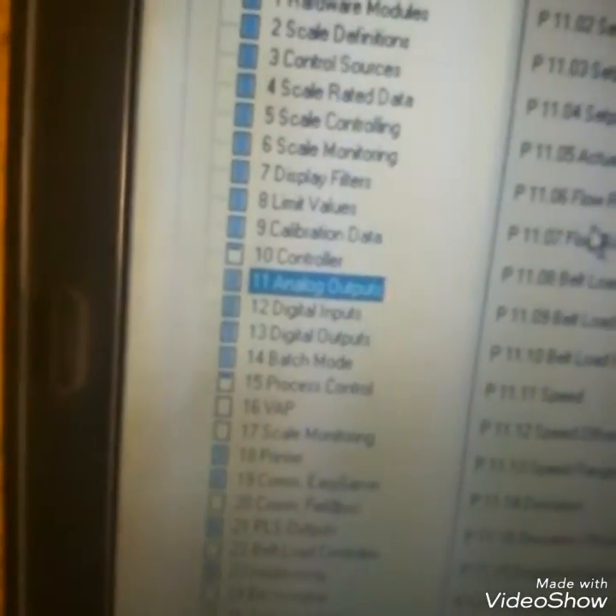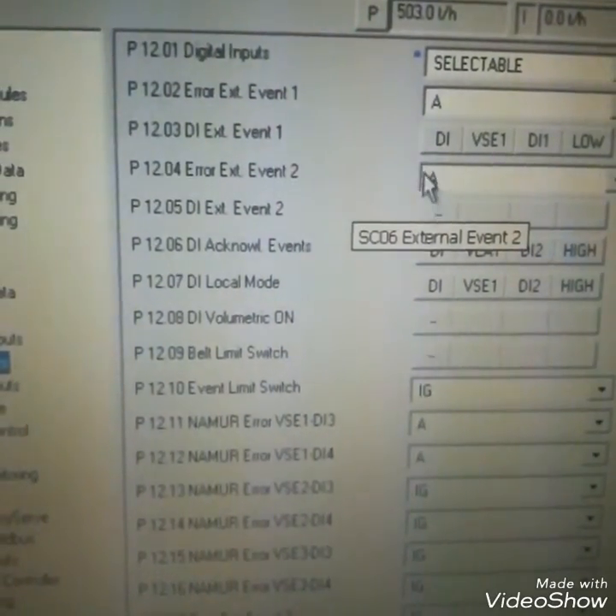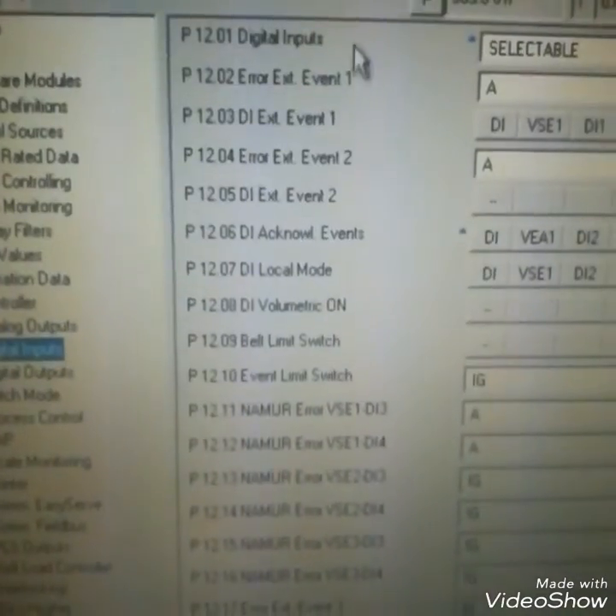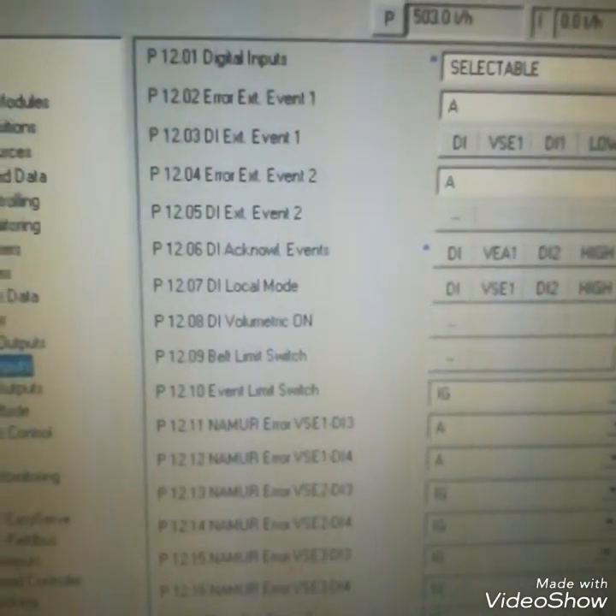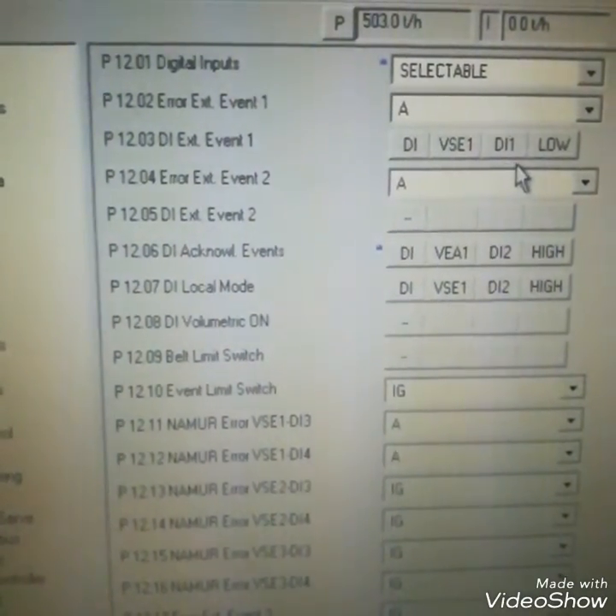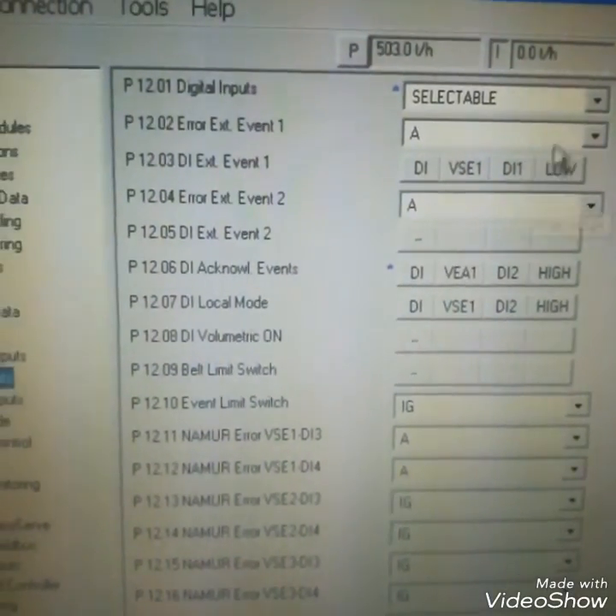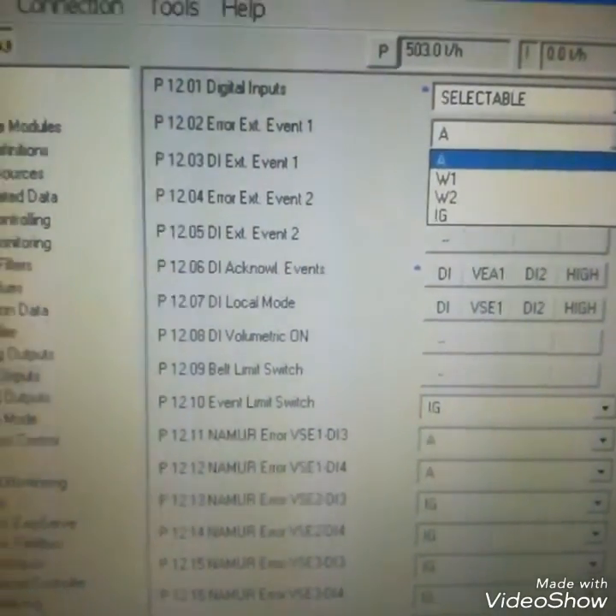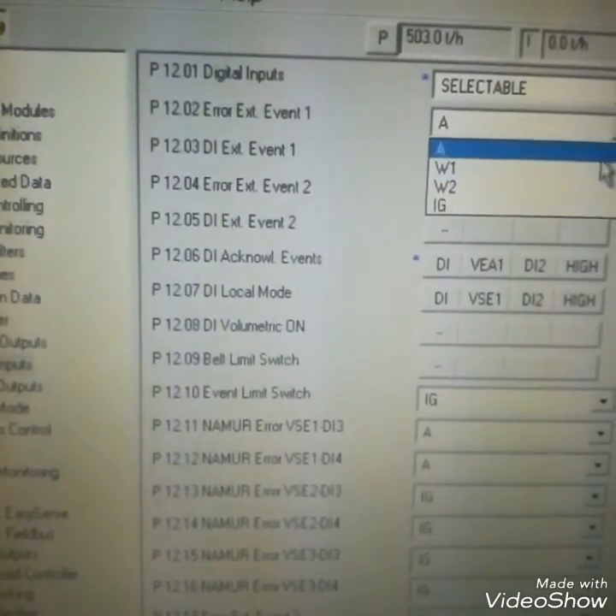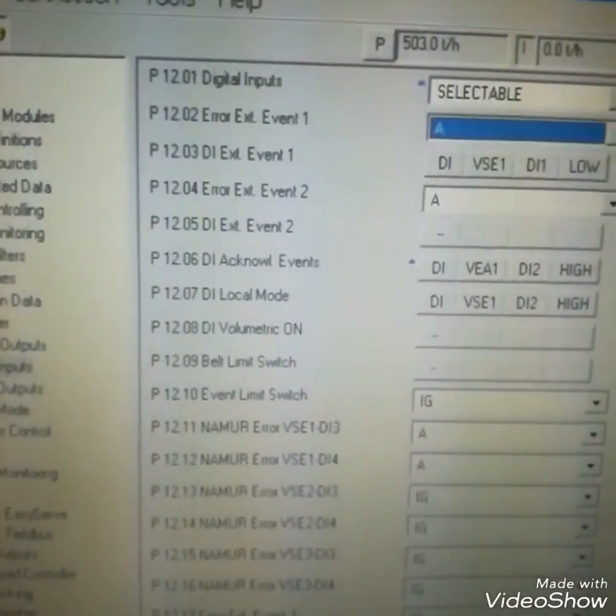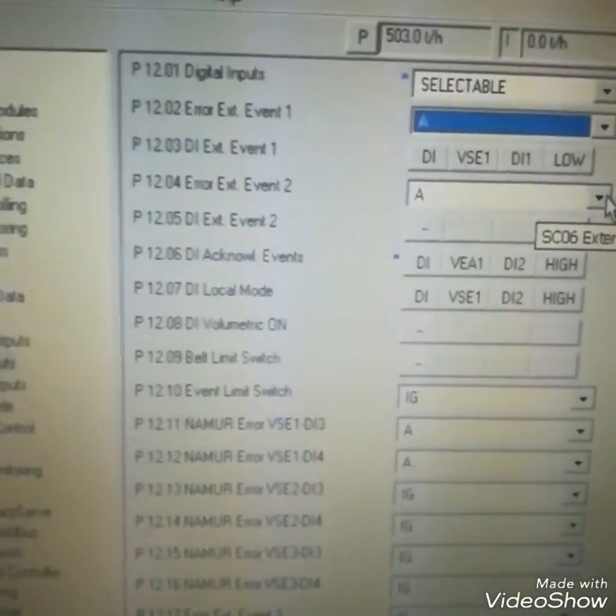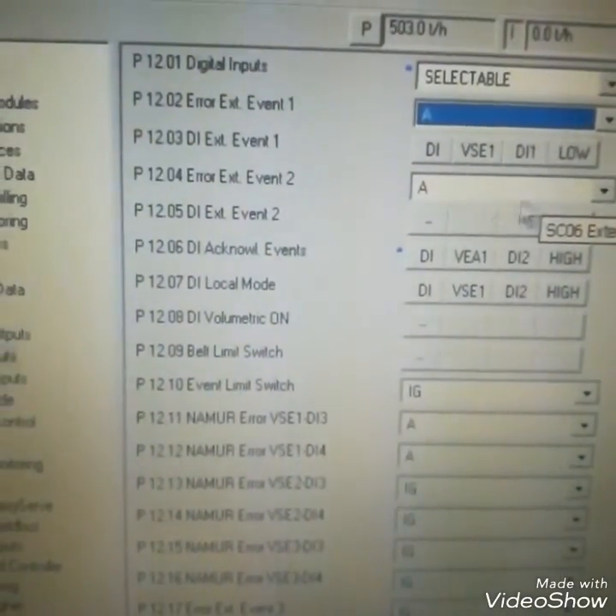Here we can adjust which output we want, 4 to 20 milliamps or 0 to 20 milliamps, and what the range is, 0 to 100 or like that. The other parameters, it's showing digital input. Suppose I want to configure a digital input. There is external event 1, it's on the VSE1 card, digital input 1. It is configured as alarm. I can configure it as warning 1, warning 2, or IG, ignore. But I want alarm because it is very critical.